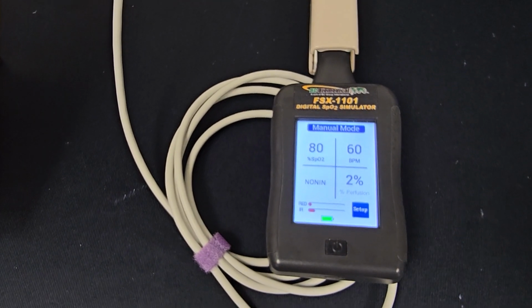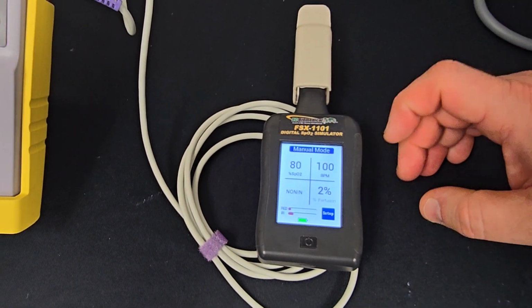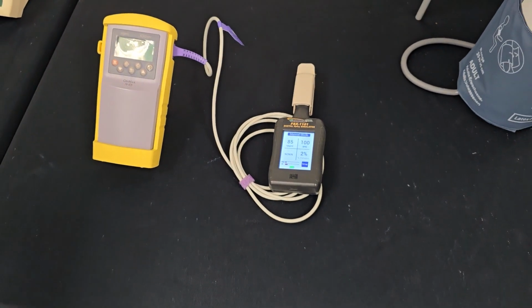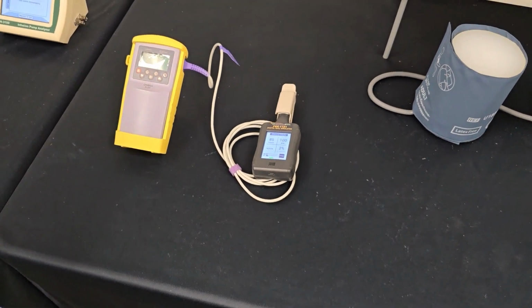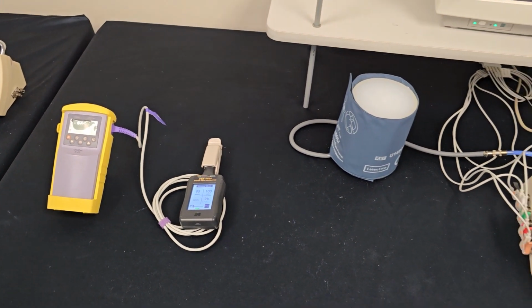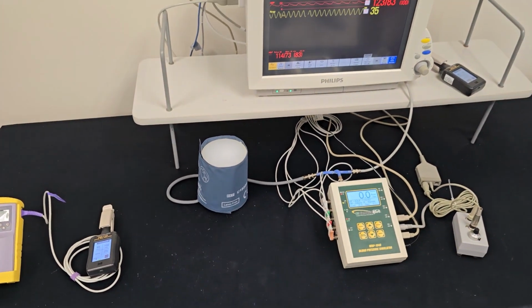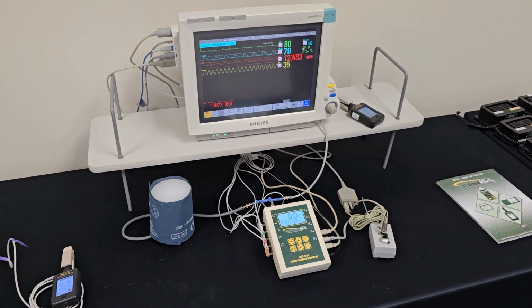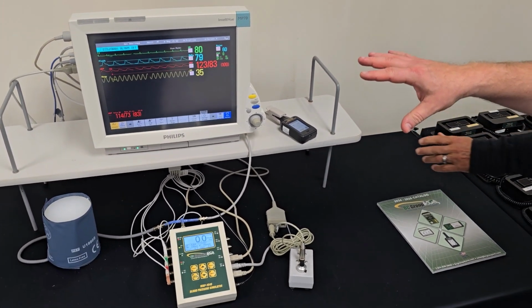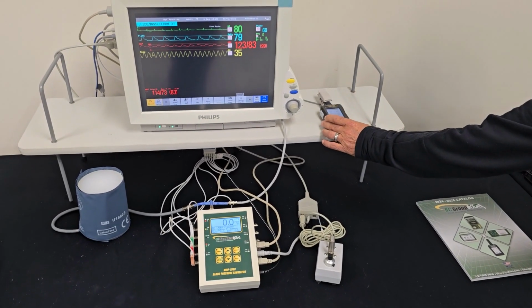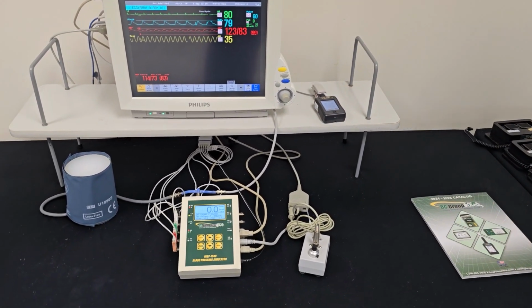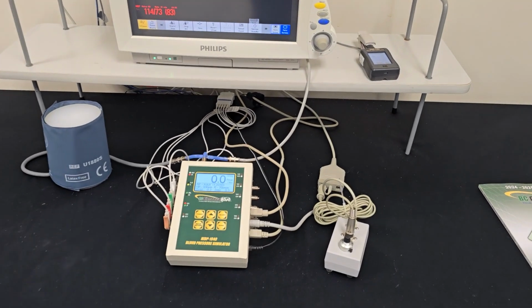Very easy to change your desired settings. This is manual mode. That means it's also got an automatic mode? It does have an automatic mode, and you can synchronize it with your patient simulator or NIBP. That way, your non-invasive blood pressure plus your SpO2, respiration, IBP, all of that is synchronized to create a true signal to the monitor. Okay.